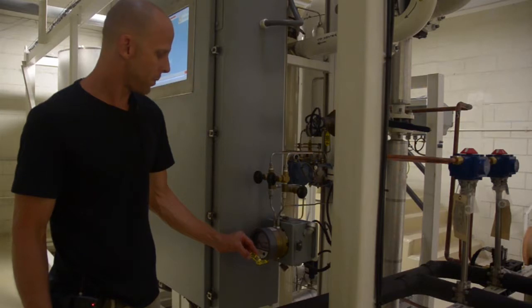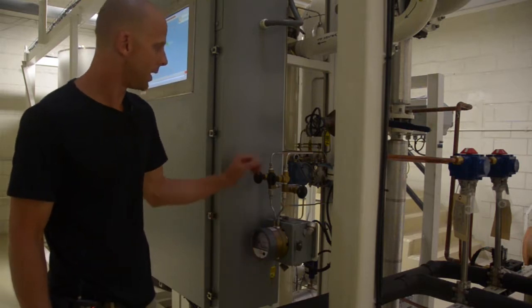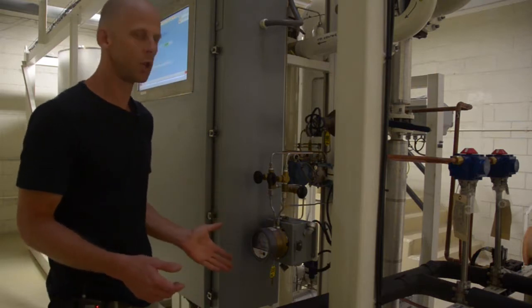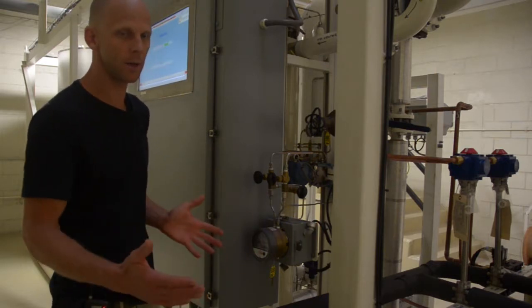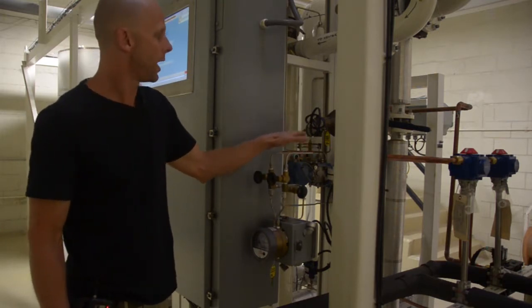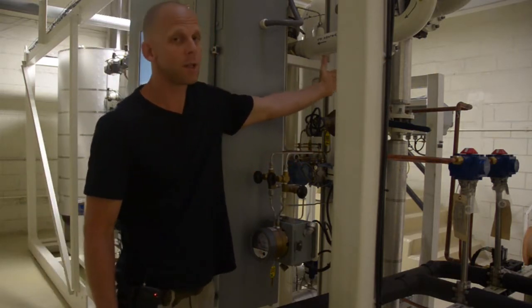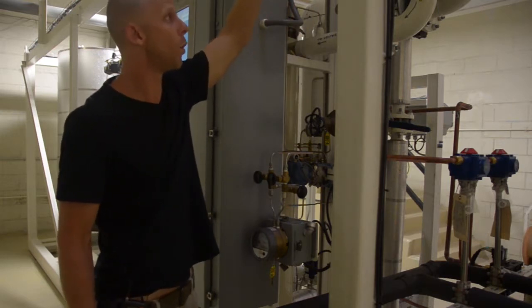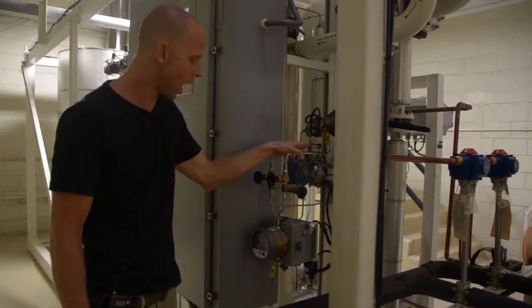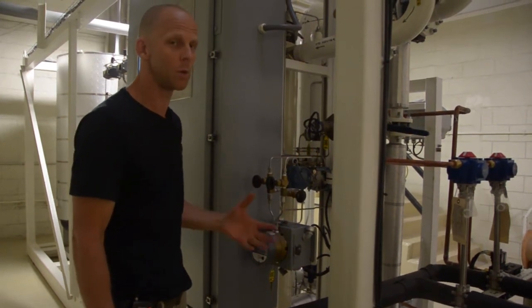You'll notice here we have a flow switch. It's a pressure differential switch, PDS 305. And this switch basically looks at the differential pressure across the heater, the pressure at the start of the heater, the pressure at the exit of the heater. And it acts as a flow switch which makes sure that we have an airflow through our heater, either a process airflow from our startup valve, or we have a flow of waste nitrogen moving through our heater. And without a flow of nitrogen or air coming through our heater, this flow switch will make sure that the heater does not turn on, okay, unless we have that flow.